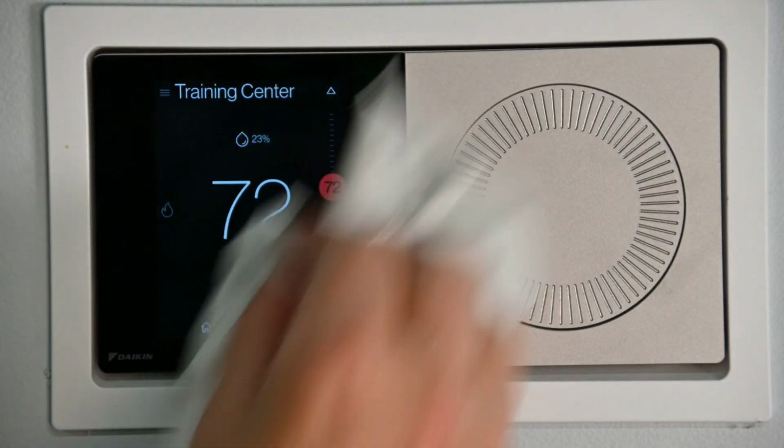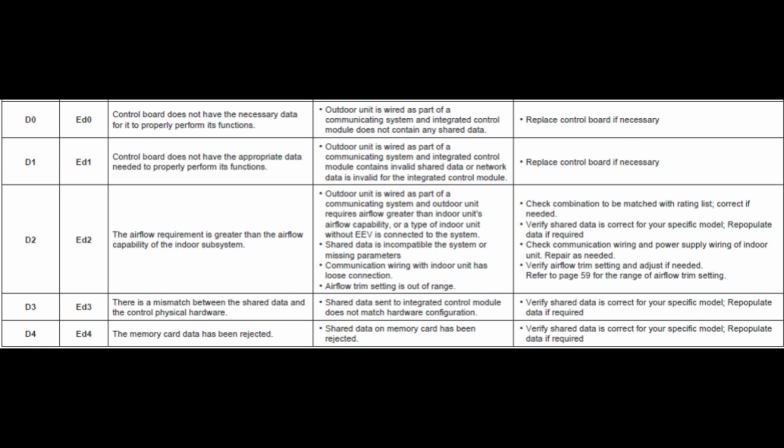All right, you just finished installing a side discharge system. Go to commission it, and we end up with the D2 error. First thing you obviously want to look at is make sure you have a matched system. Running the AHRI numbers, they should be fine.